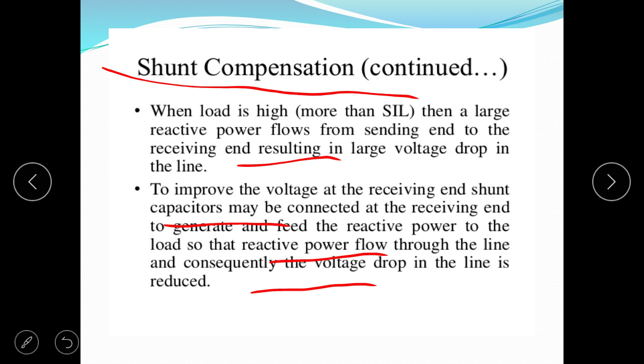To control the receiving end voltage, a bank of capacitors is used. What is a capacitor bank? In a capacitor bank, a large number of capacitors are connected in parallel and installed at the receiving end, and a suitable number of capacitors are switched in during high load conditions depending upon the load demand. Thus, the capacitor provides leading var to partially meet the reactive power demand of the load to control the voltage. It means a shunt capacitor provides or injects reactive power according to the requirement of the load. But in the case of a series capacitor, when there is a sudden change in load, the capacitor injects reactive power directly.